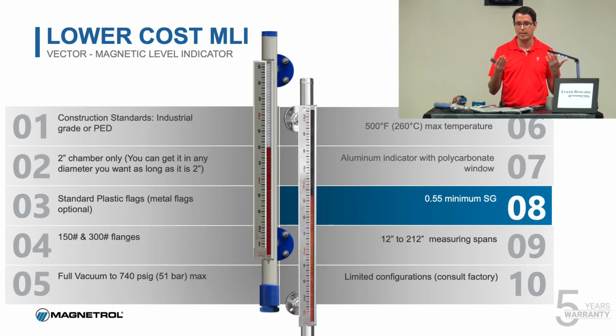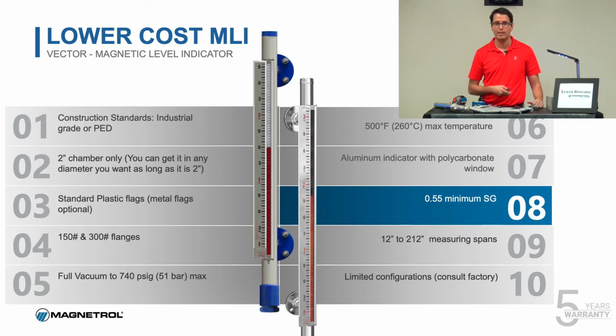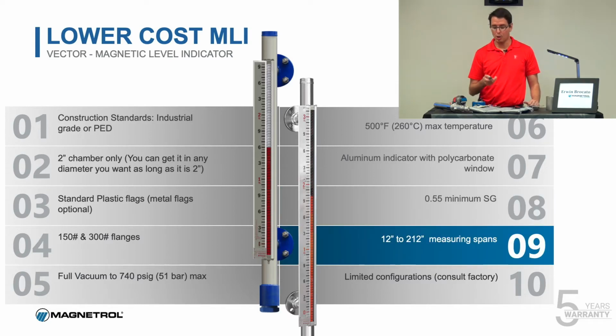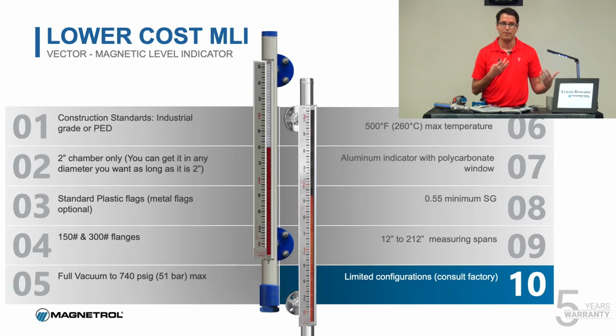So usually oil is anywhere from 0.7 to maybe 0.8 or something like that. Diesel is usually 0.8 as well. The lighter the hydrocarbon, the lower the density, and this may not be the product for that particular application. But if it's something like a strong base, those are going to have really high specific gravities. Water's 1, and a strong base is going to be maybe 1.1 or 1.2. Measuring spans, it says it right there, 212 inches is the max. That's actually pretty reasonable for one of these devices. And limited configurations, no specials. We try to simplify the device as much as possible to keep the cost low.